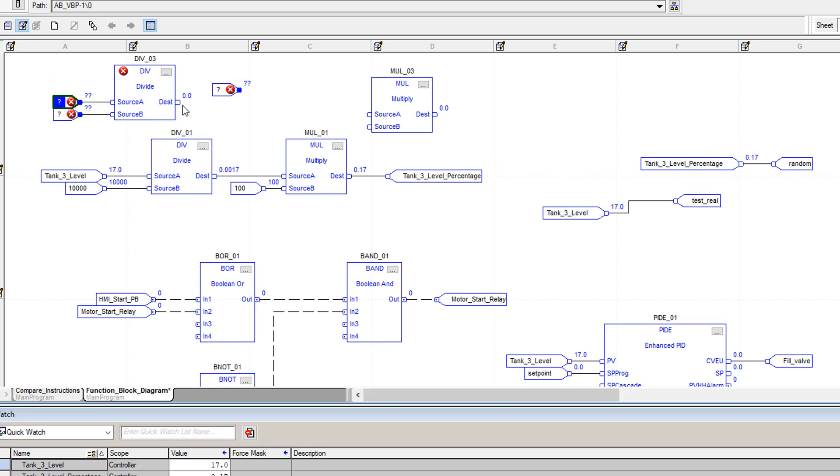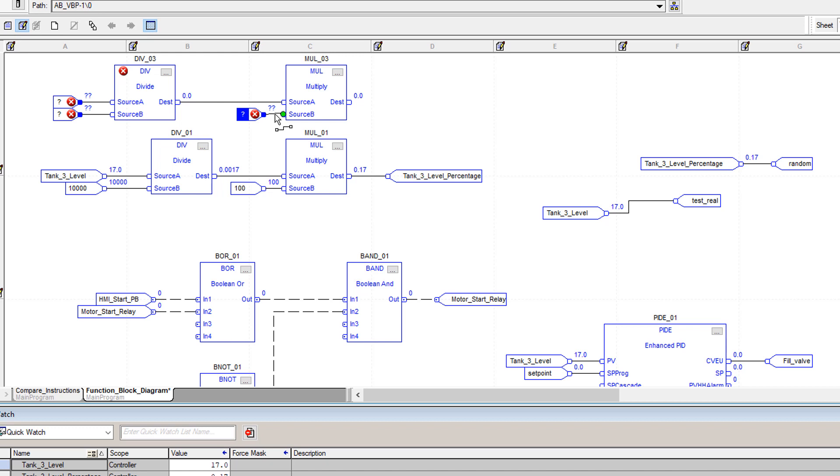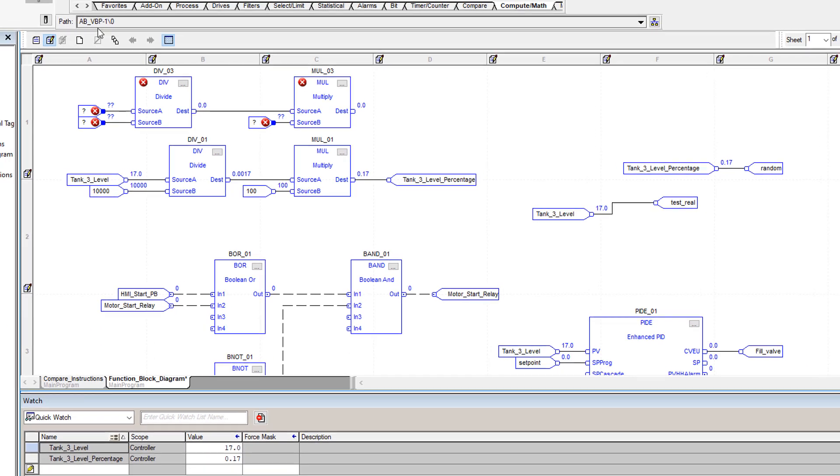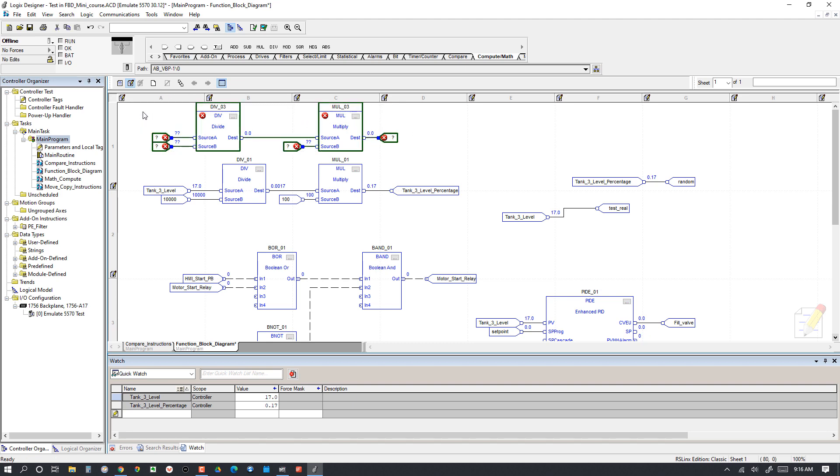You would just connect one of your input references to Source B, one of your input references to Source A. Then your output of the divide instruction can just connect to Source A. You just click and drag it, and then when it turns green, you drop it. Again, with your input reference, you click here and drag it. When it turns green, we drop it. The destination, we don't have to put an output tag, which is nice. But if you want to have an actual tag associated with this calculation, then you drag this and drop it there. That's basically how it works.